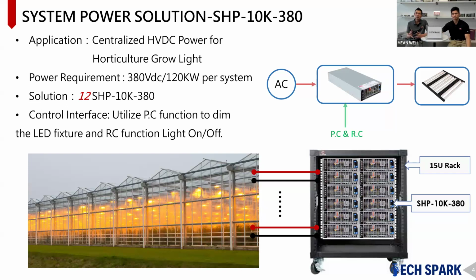Yeah, this system power solution is for a centralized power application where the customer needed a system, a cabinet power that they put inside an electrical room and then bring the power into the grow room. The requirement was multiple systems, each system being 120 kilowatts - very high - and they wanted 12 individual outputs, each output being 10 kilowatts to power 10 LEDs. The system is very high power, so the input voltage had to be 480 volts, not 208.